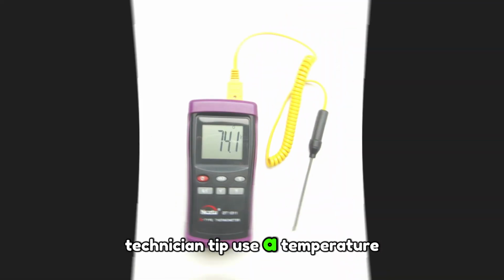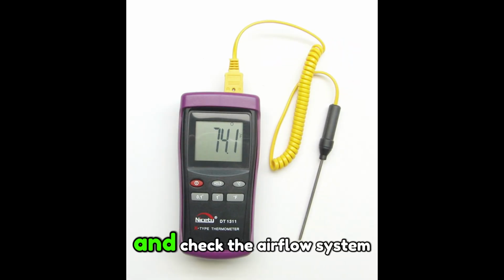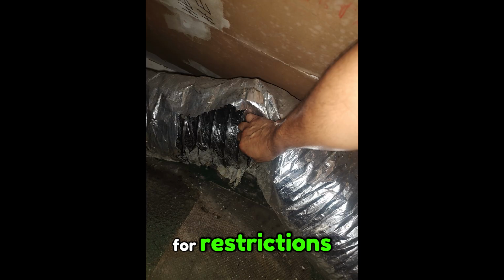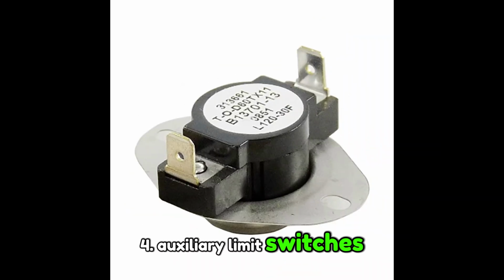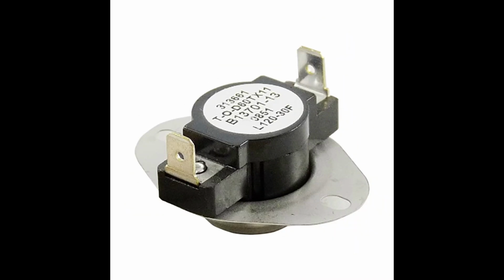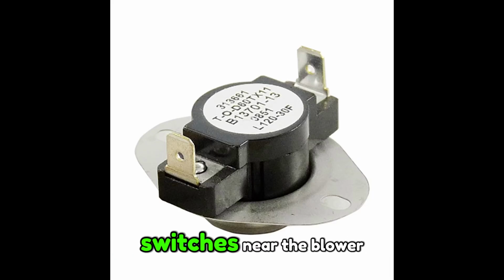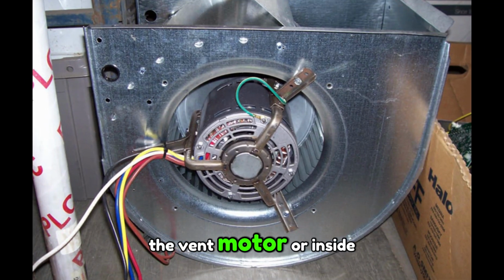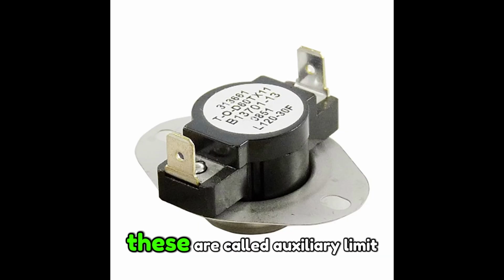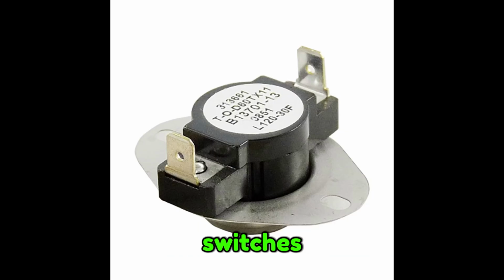Technician tip: use a temperature probe to verify readings and check the airflow system for restrictions. 4. Auxiliary limit switches, extra protection. Some furnaces include additional limit switches near the blower, the vent motor, or inside compartments. These are called auxiliary limit switches. They act as backup safety controls and may trigger a hard lockout if tripped.